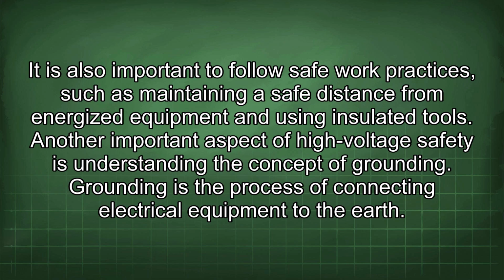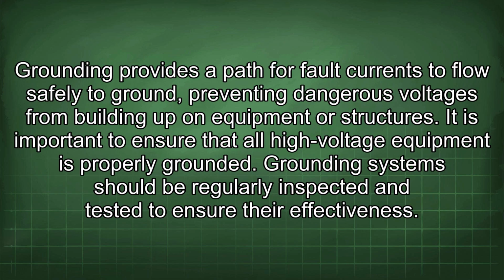Another important aspect of high-voltage safety is understanding the concept of grounding. Grounding is the process of connecting electrical equipment to the earth. Grounding provides a path for fault currents to flow safely to ground, preventing dangerous voltages from building up on equipment or structures. It is important to ensure that all high-voltage equipment is properly grounded. Grounding systems should be regularly inspected and tested to ensure their effectiveness.